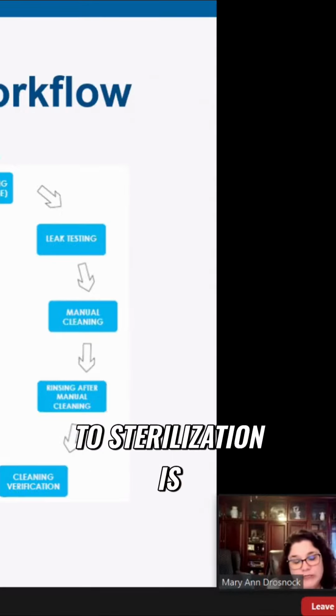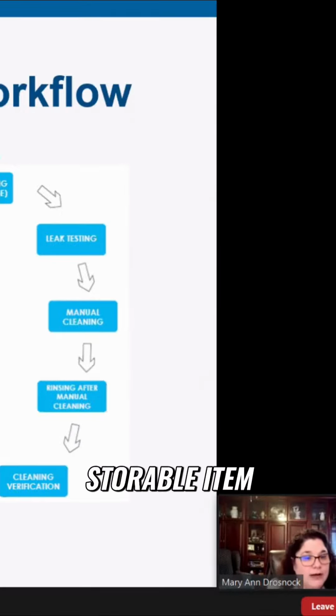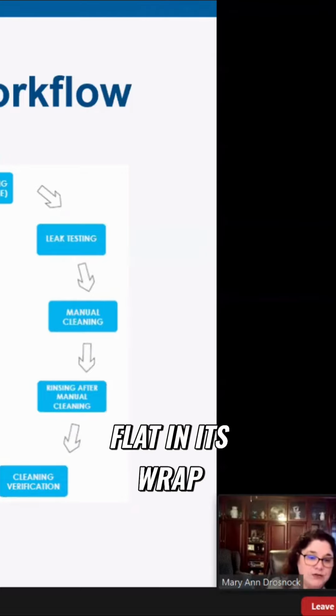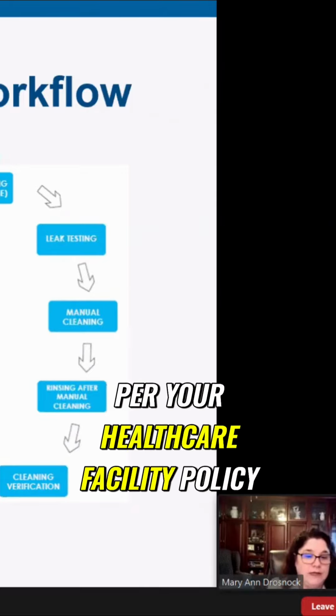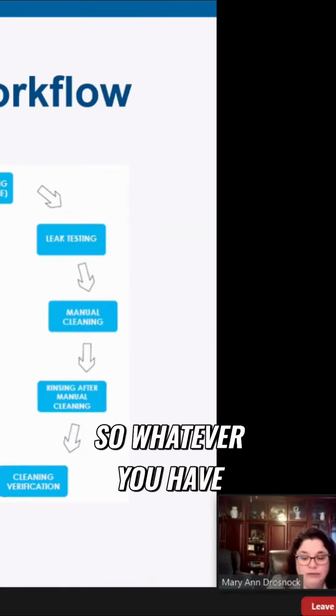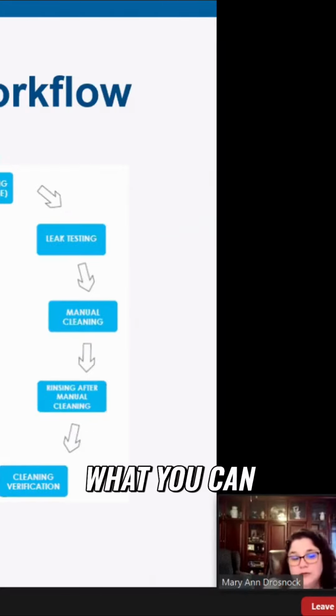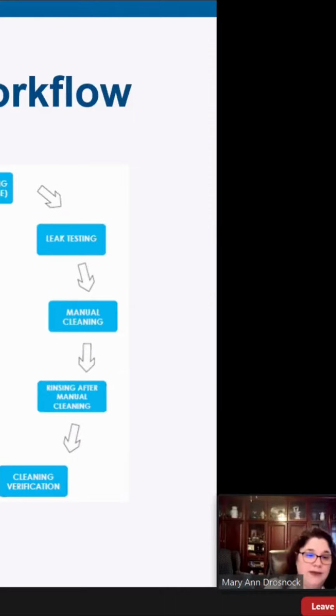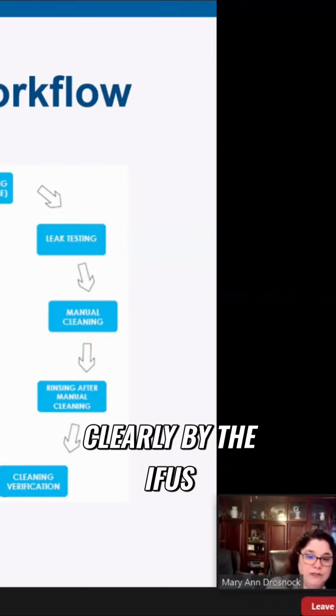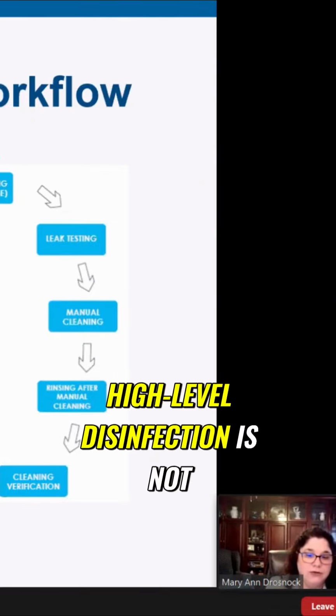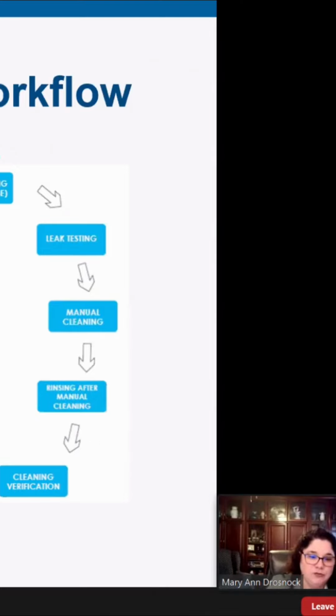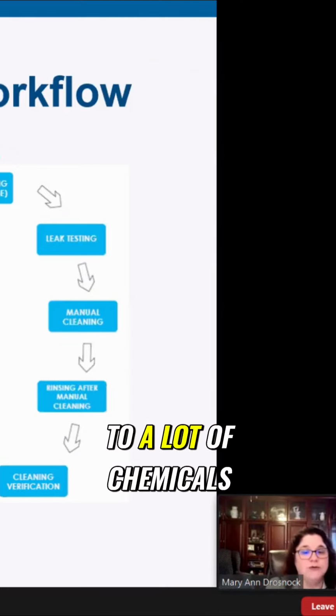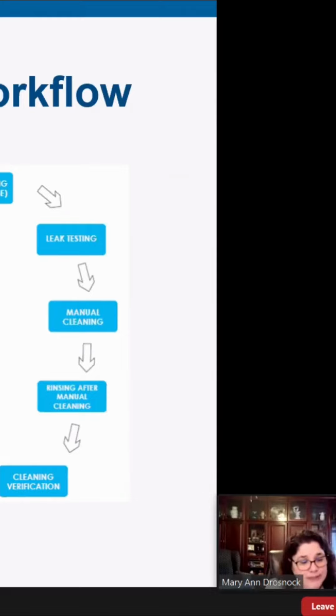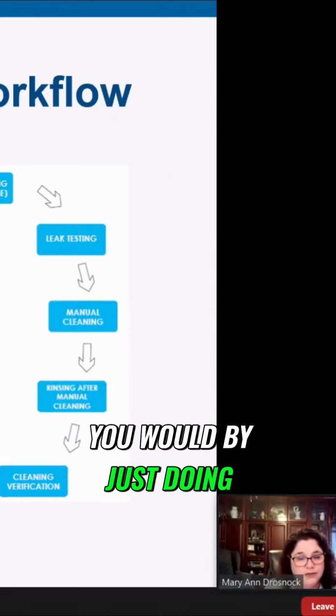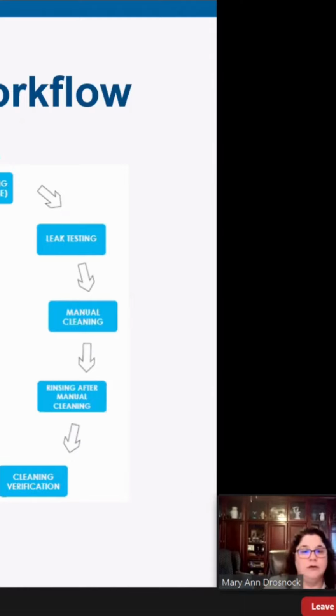And what's great about moving to sterilization is you have a wrapped storable item that can stay flat in its wrap per your healthcare facility policy on sterilized items. So whatever you have for everything else is what you can do with these sterilized endoscopes. And then we go back to reuse from there. So we see clearly by the IFUs that high-level disinfection is not included as part of the sterilization process. You're really subjecting that scope to a lot of chemicals and will get damage potentially much earlier than you would by just doing one system or the other.